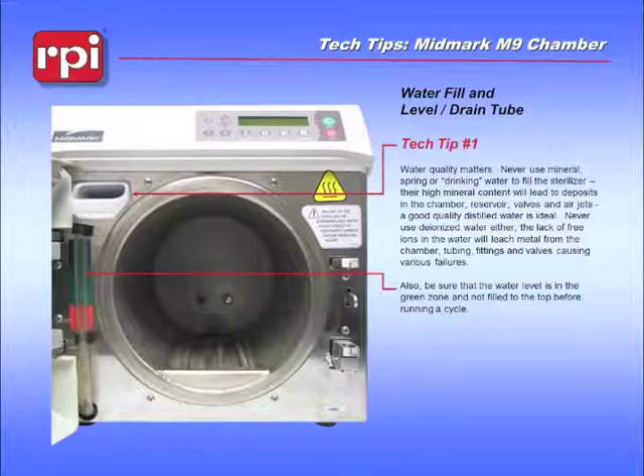The other thing you want to avoid is using deionized water. Deionized water has all its free ions removed, and it will look for free ions anywhere it can find them, including the metal of the chamber, the metal of the tubing, or of the valves. You cannot use deionized water in any sterilizers.